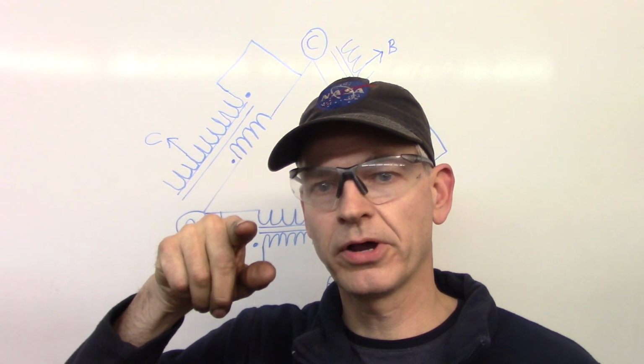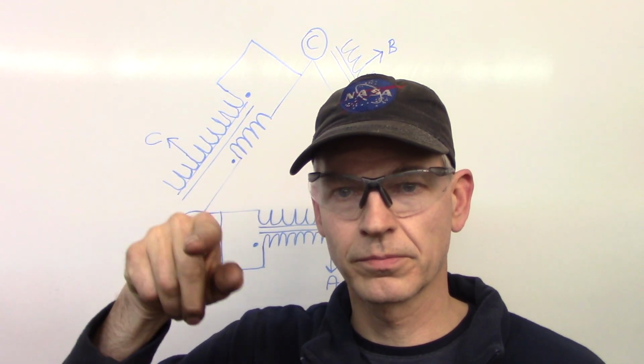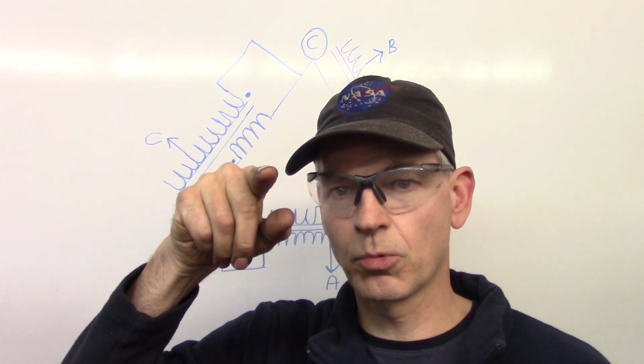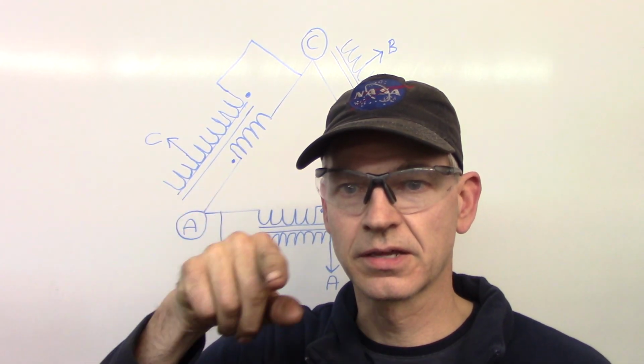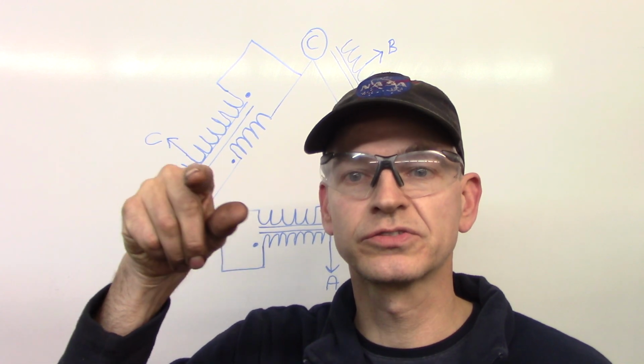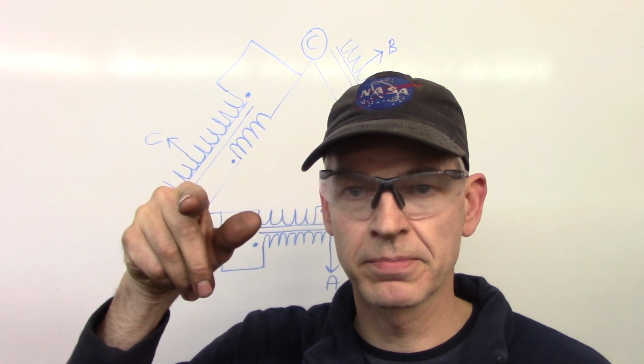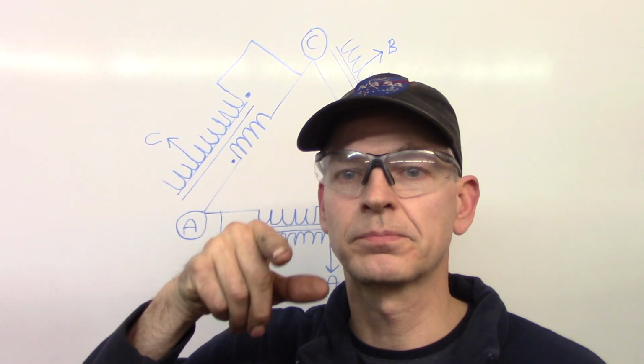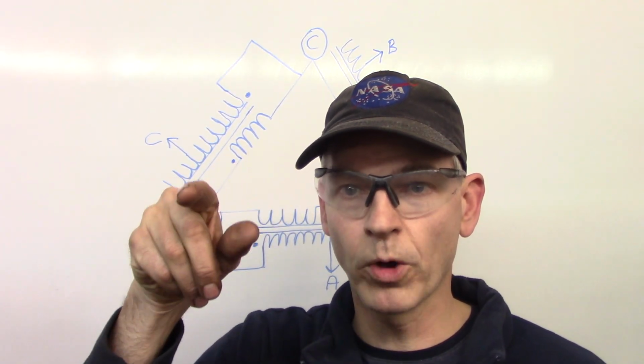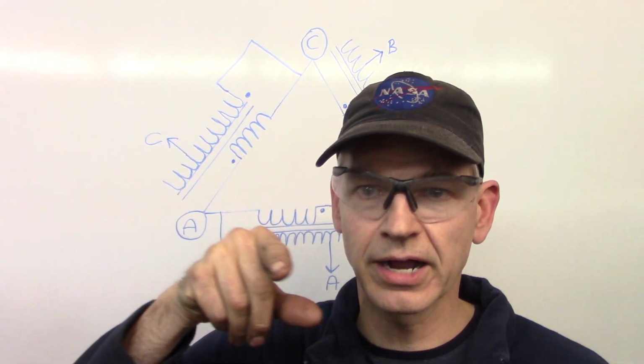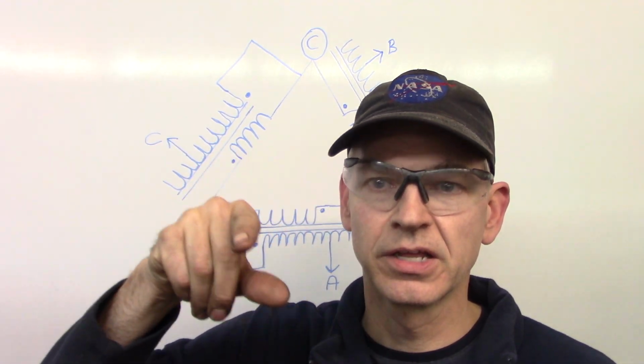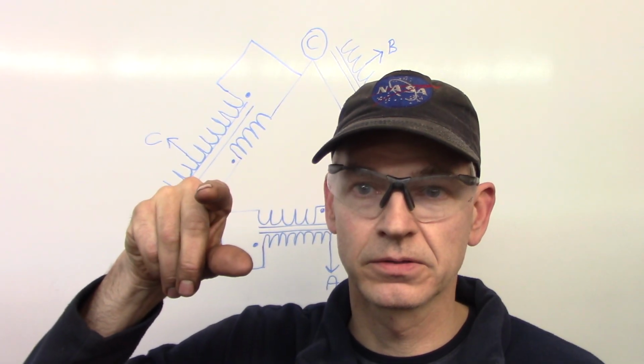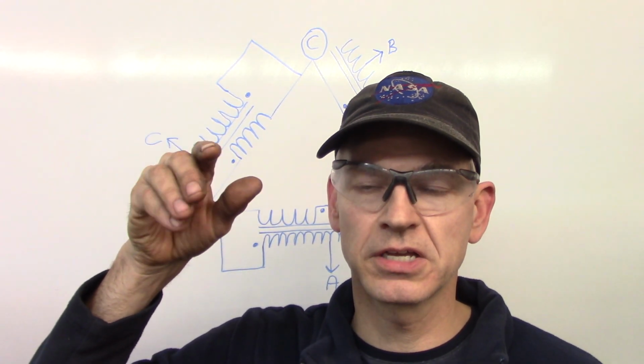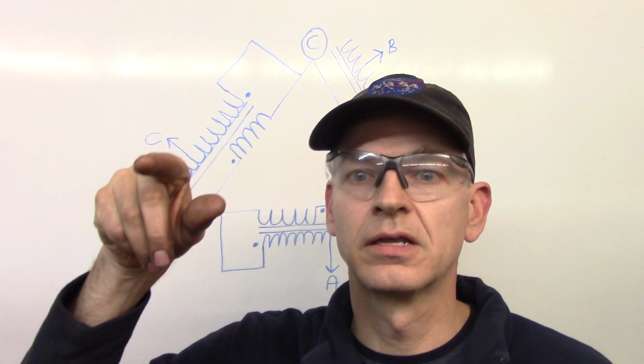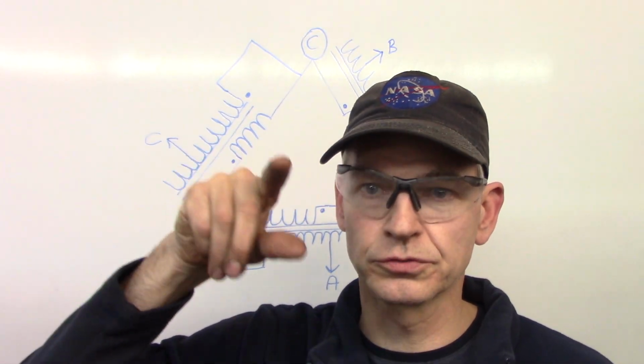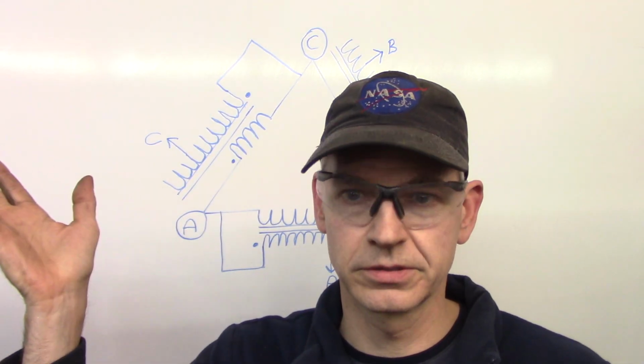If your primary in the transformer is clockwise, and your secondary is also wired clockwise, that's a boost - it increases the voltage, it boosts the voltage. On the other hand, if your primary is clockwise and you wire the secondary counterclockwise, backwards from the first, then it's a buck configuration, which means instead of boosting the voltage, it bucks the voltage - it lowers the voltage going out.